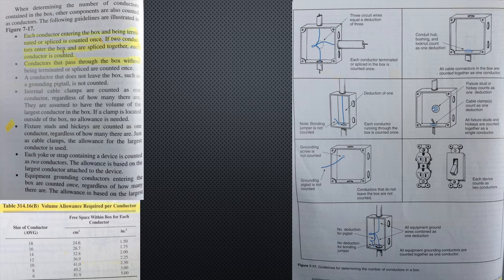Each yoke or strap containing the device is counted as two conductors. The allowance is based on the largest conductor attached to the device.